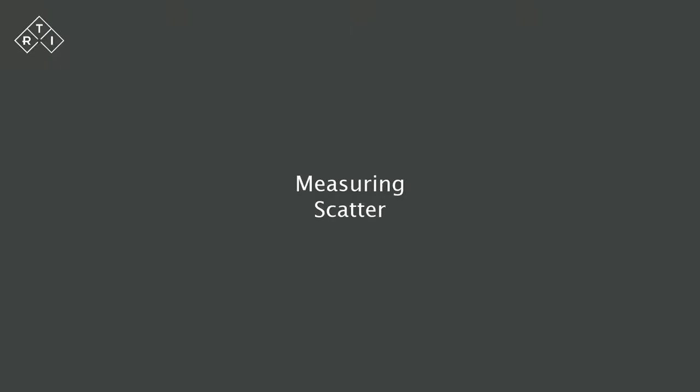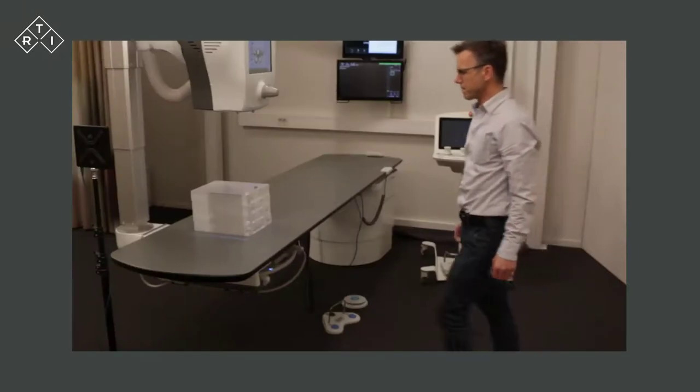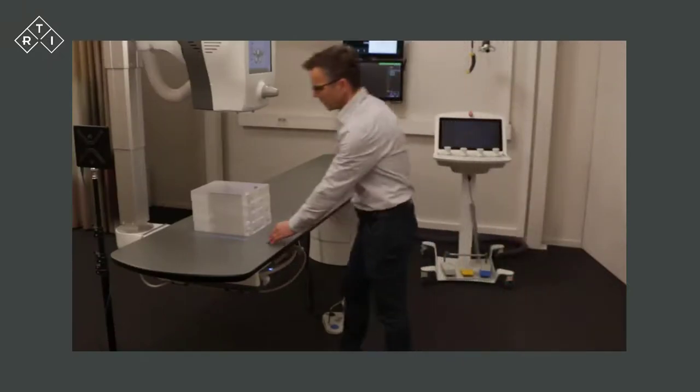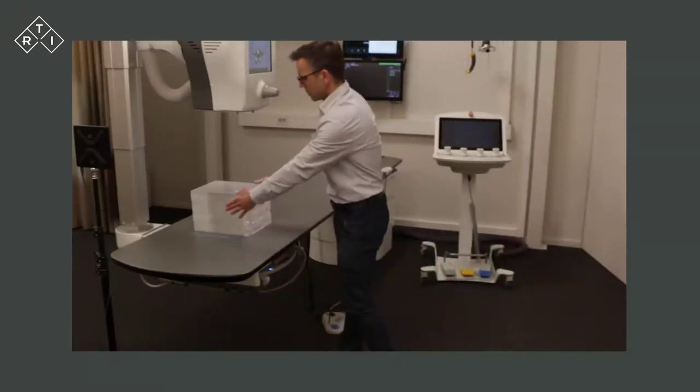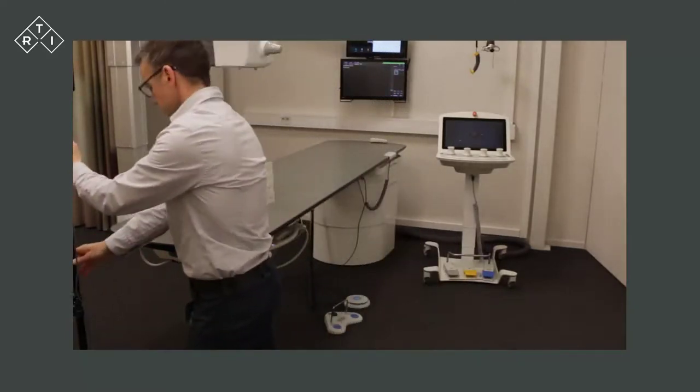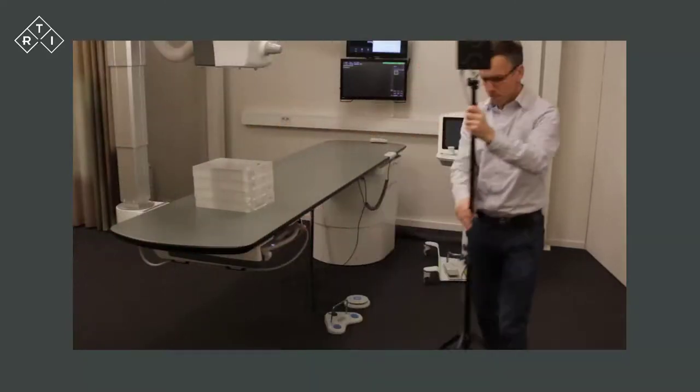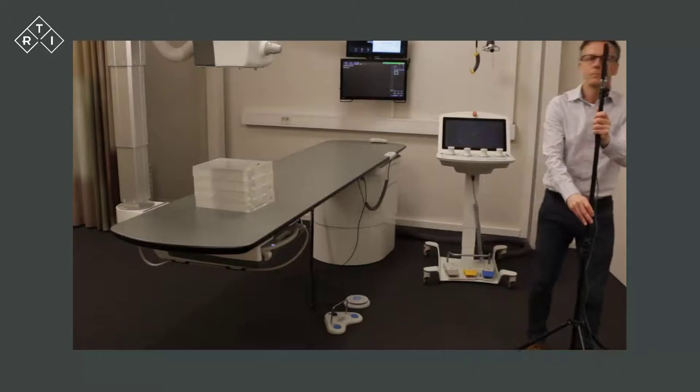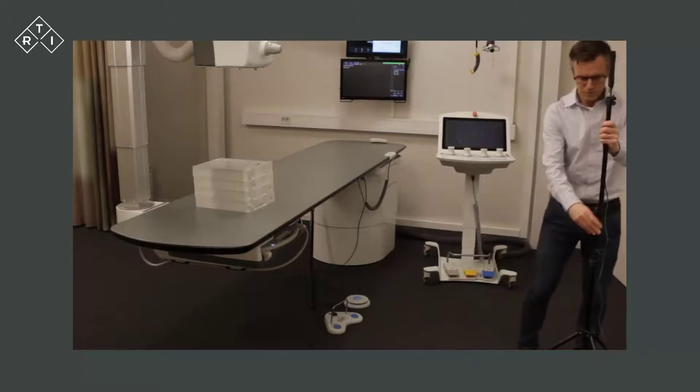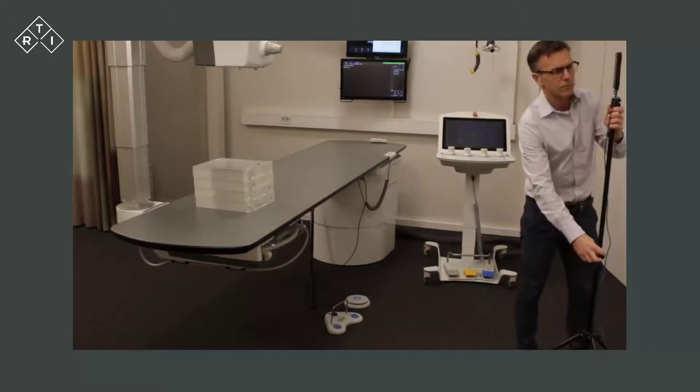A common method to measure scatter is to place a stack of PMMA slabs under the tube and open the collimator so that the X-ray field is slightly larger. Place the RTI Scatter Probe in the desired location.